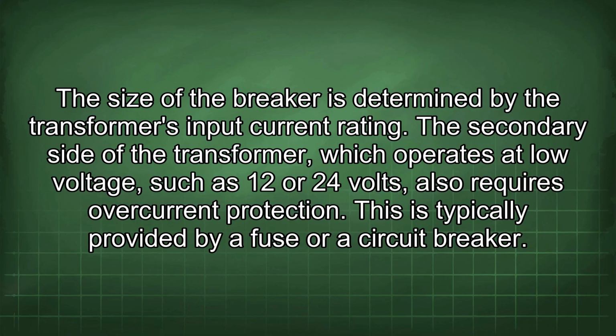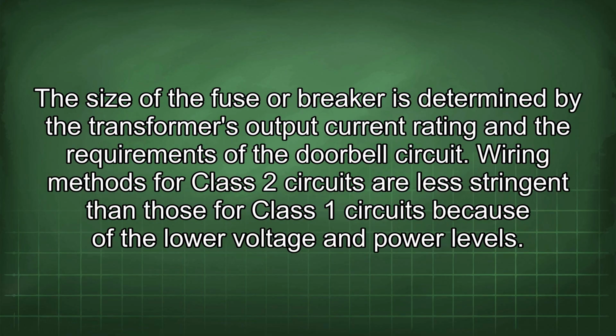The secondary side of the transformer, which operates at low voltage, such as 12 or 24 volts, also requires overcurrent protection. This is typically provided by a fuse or a circuit breaker. The size of the fuse or breaker is determined by the transformer's output current rating and the requirements of the doorbell circuit. Wiring methods for Class 2 circuits are less stringent than those for Class 1 circuits because of the low voltage and power levels.